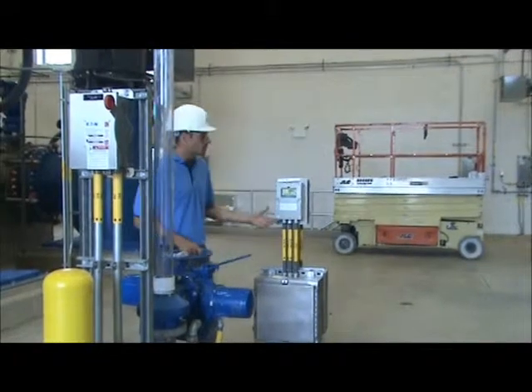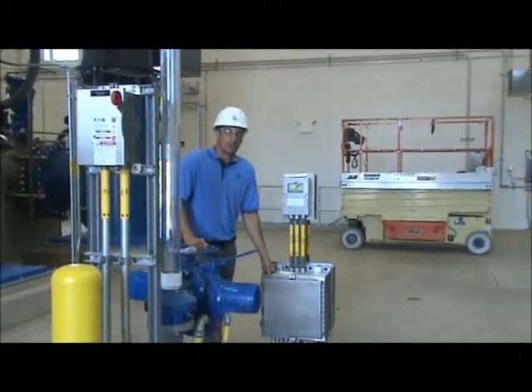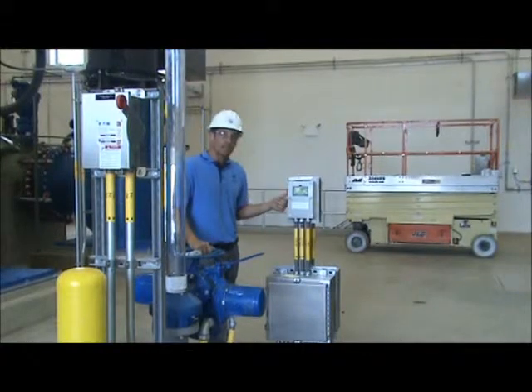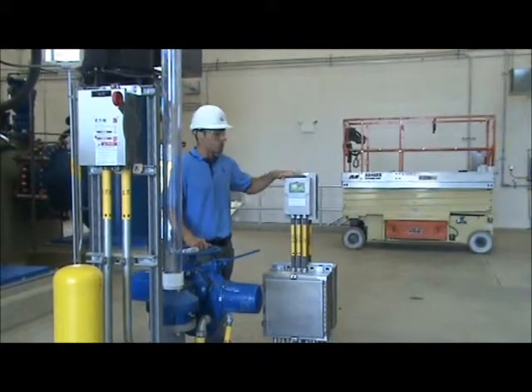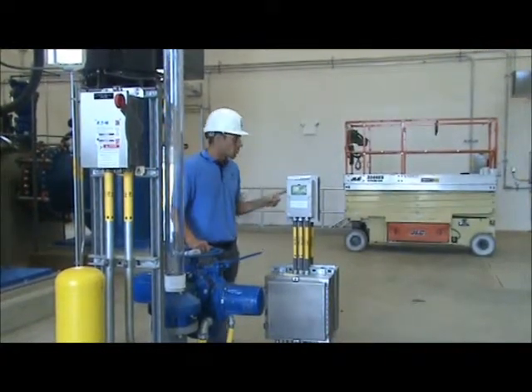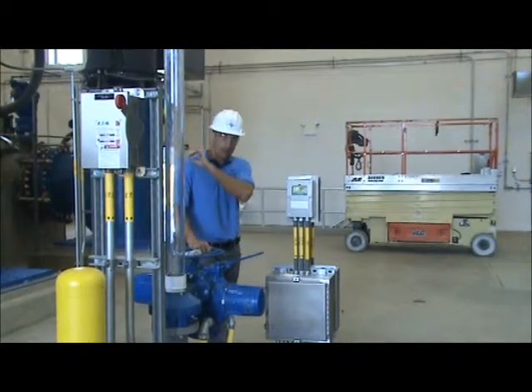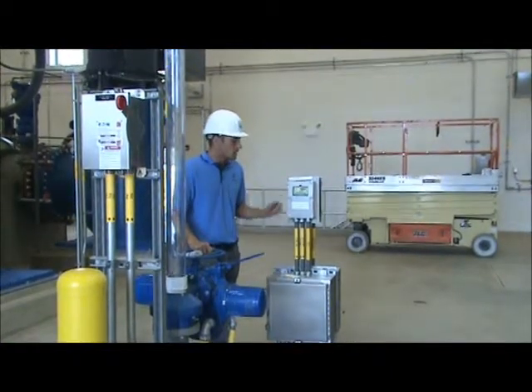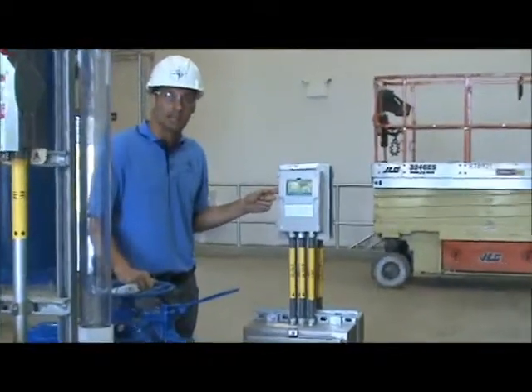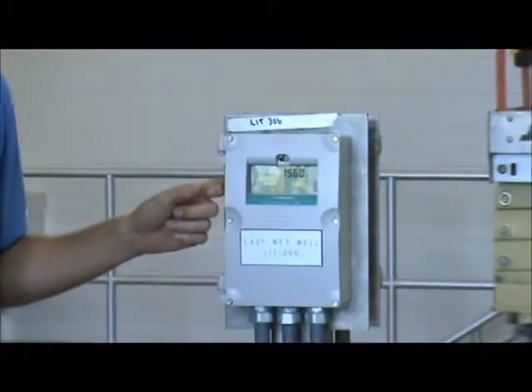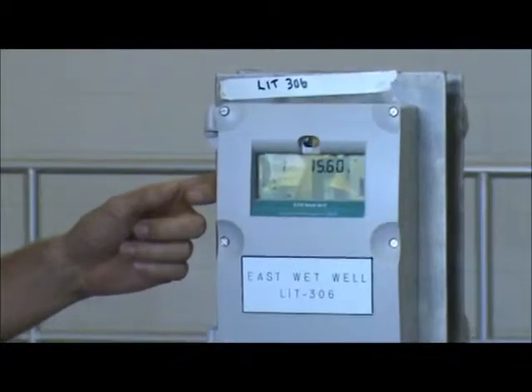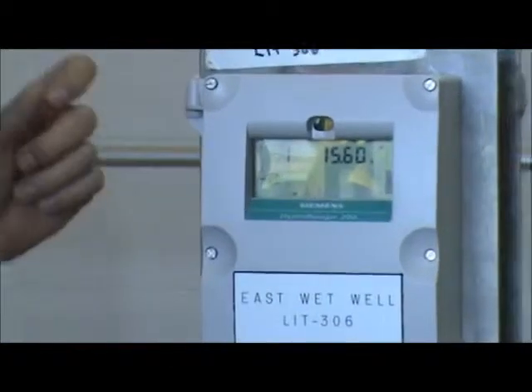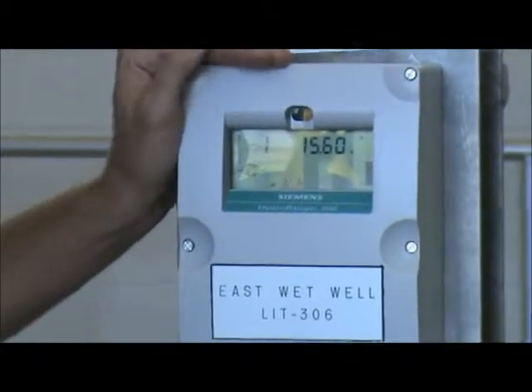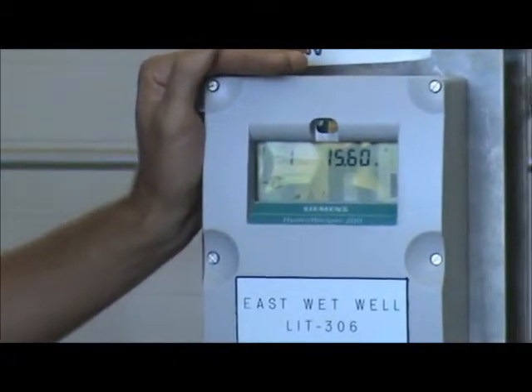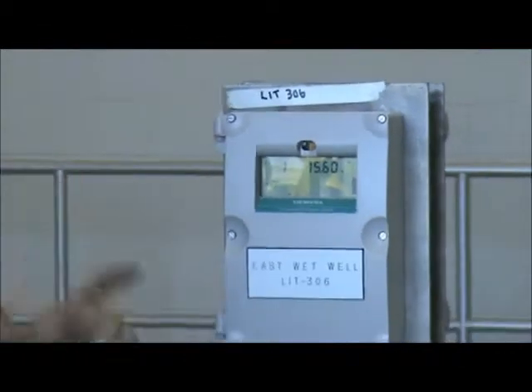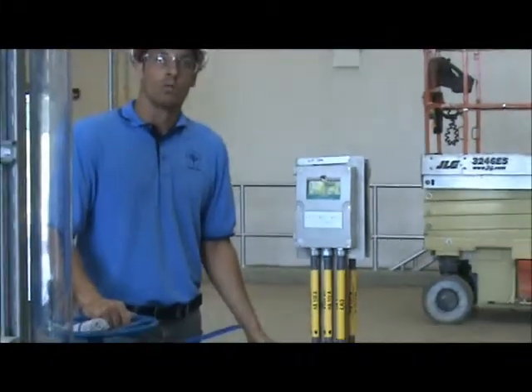Here are our level monitors. They're the Siemens HydroRanger 200s. And what we get from these is 2 units, 2 wet wells. Each one sends to 2 of our controllers. We get a 4 to 20 signal from these. And then there's also a failure, a digital contact that we take back, which signals either loss of power to the unit itself or a loss of echo from the transducer. Then also in these wet wells, there's low level floats.